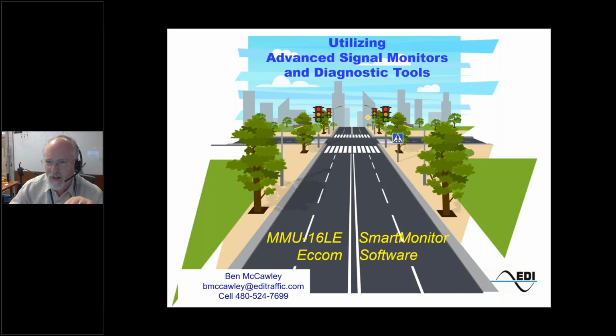So really the LED guard isn't saying, okay, this LED is on, this LED is on. It's more of a catastrophic issue. So it isn't looking at just one of three heads, it's looking at that overall head. To give you an example, if one of the three heads is dark and the other two are good, it won't go into flash. All right, that's better. Yeah, that explains it more to where we want it now.